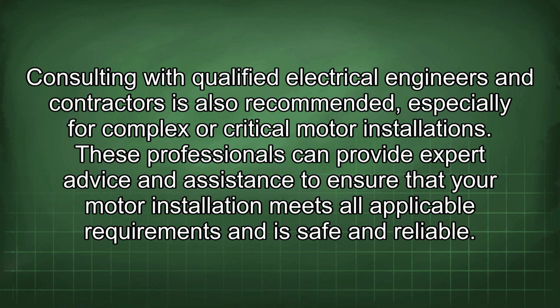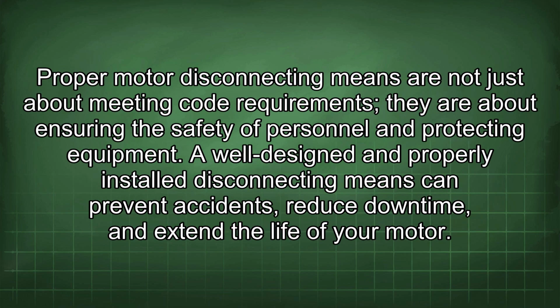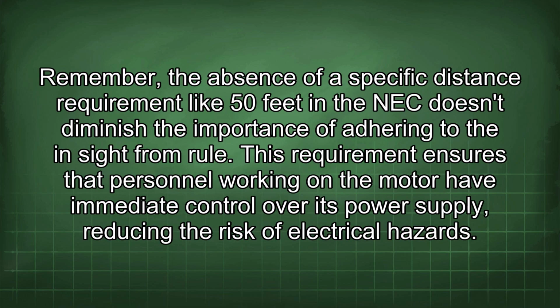Proper motor disconnecting means are not just about meeting code requirements, they are about ensuring the safety of personnel and protecting equipment. A well-designed and properly installed disconnecting means can prevent accidents, reduce downtime, and extend the life of your motor. Remember, the absence of a specific distance requirement like 50 feet in the NEC doesn't diminish the importance of adhering to the in-sight from rule.